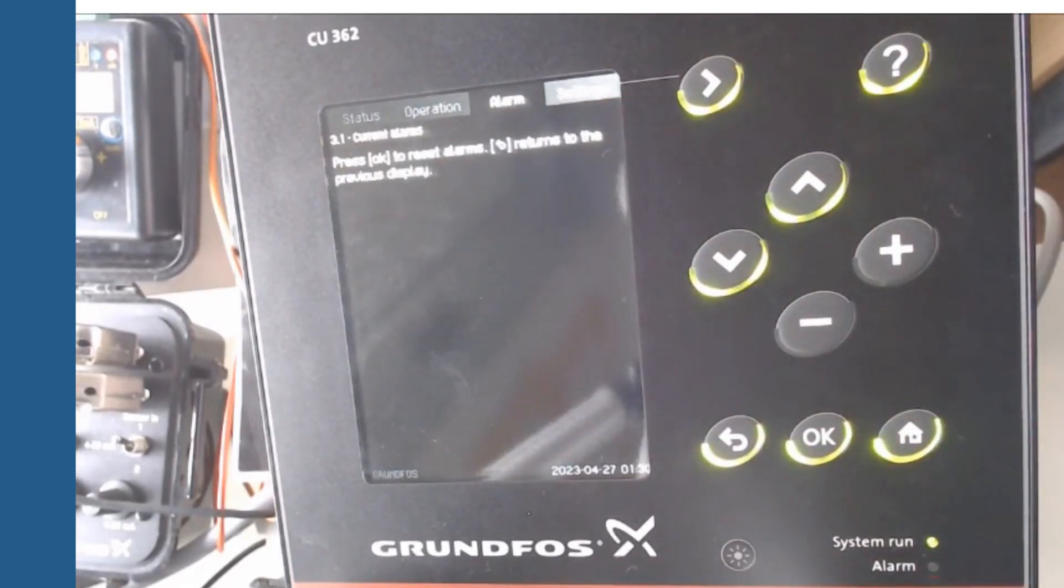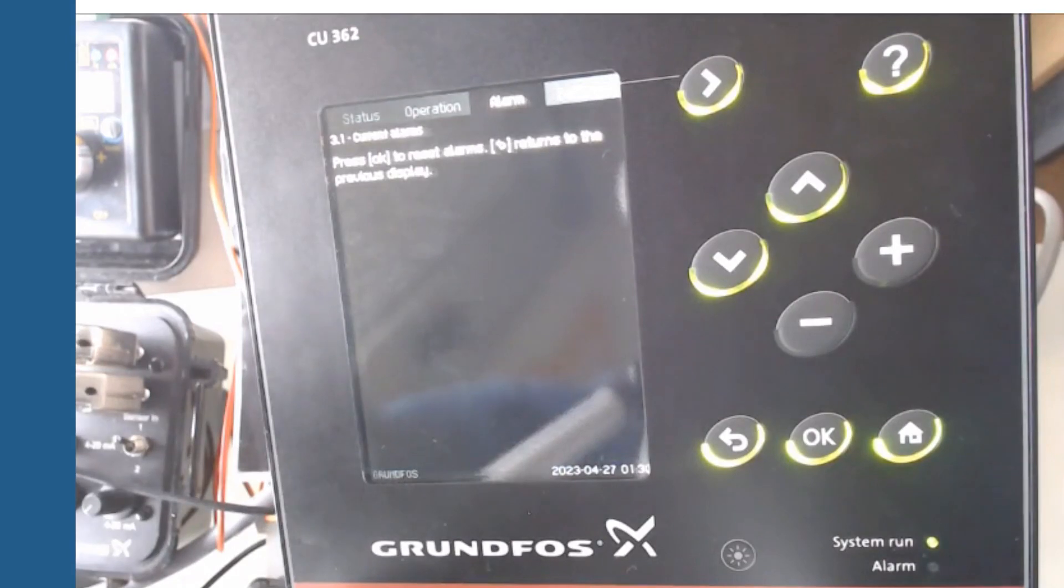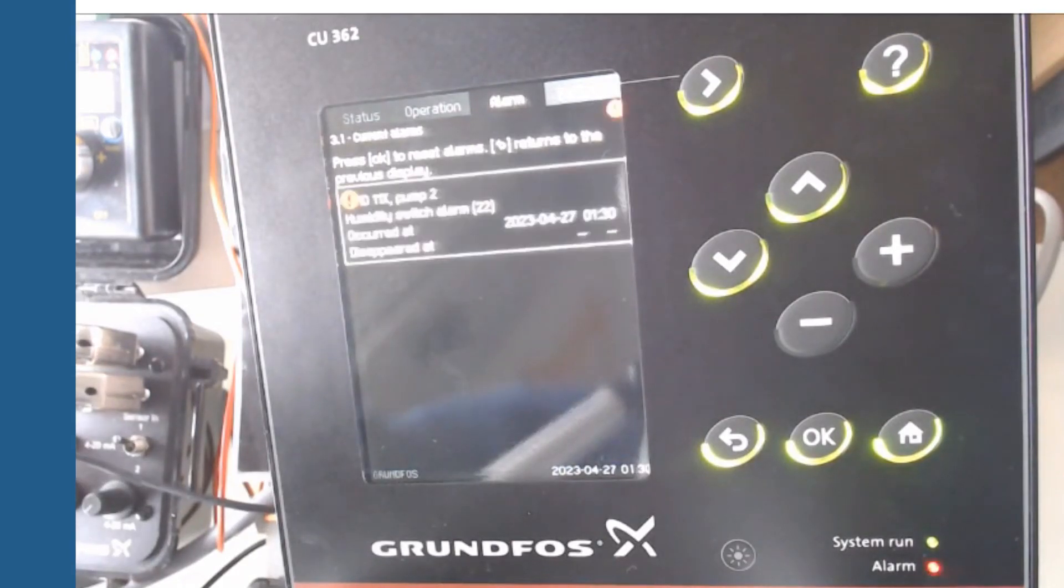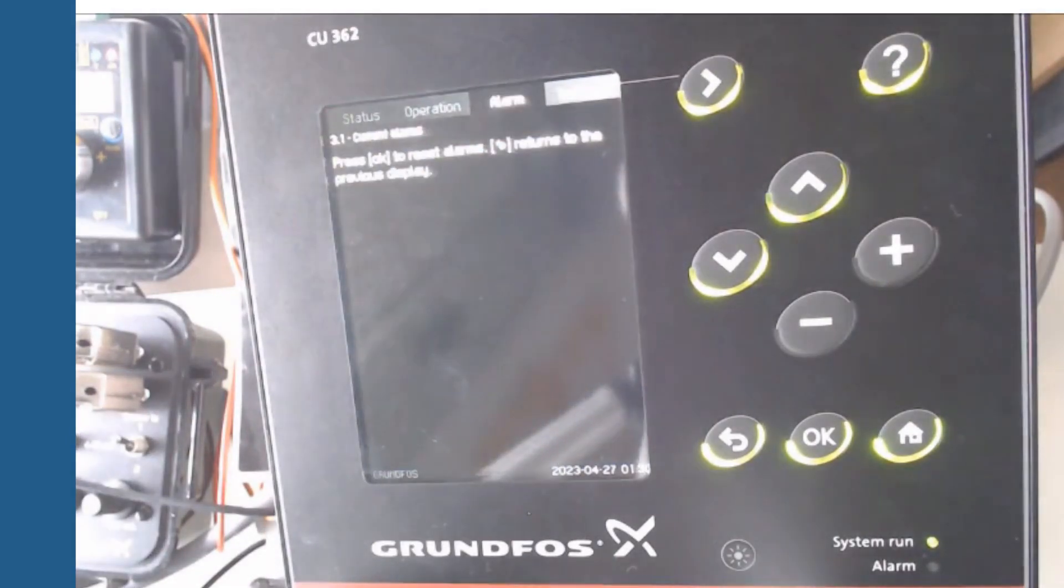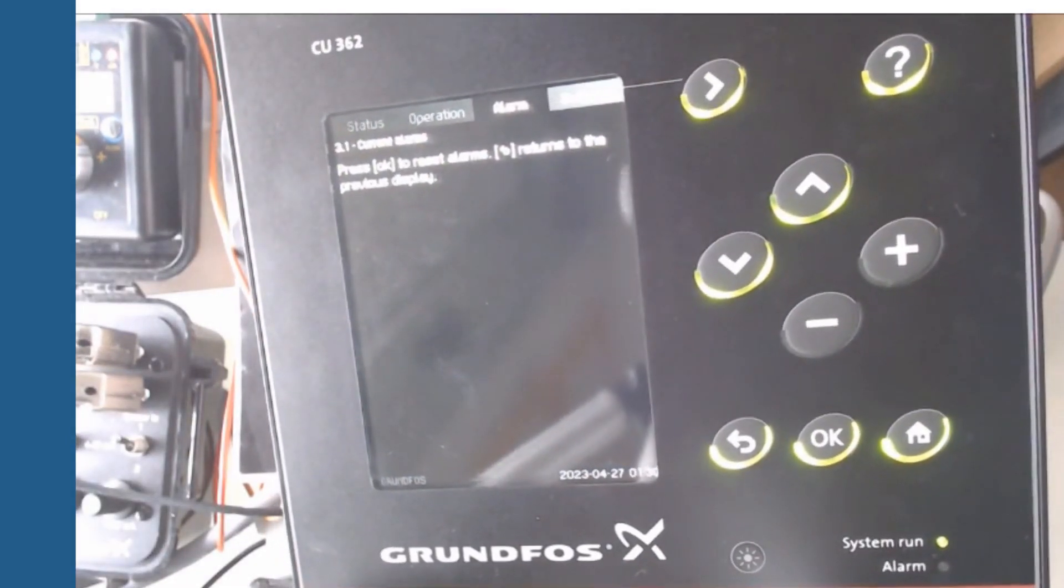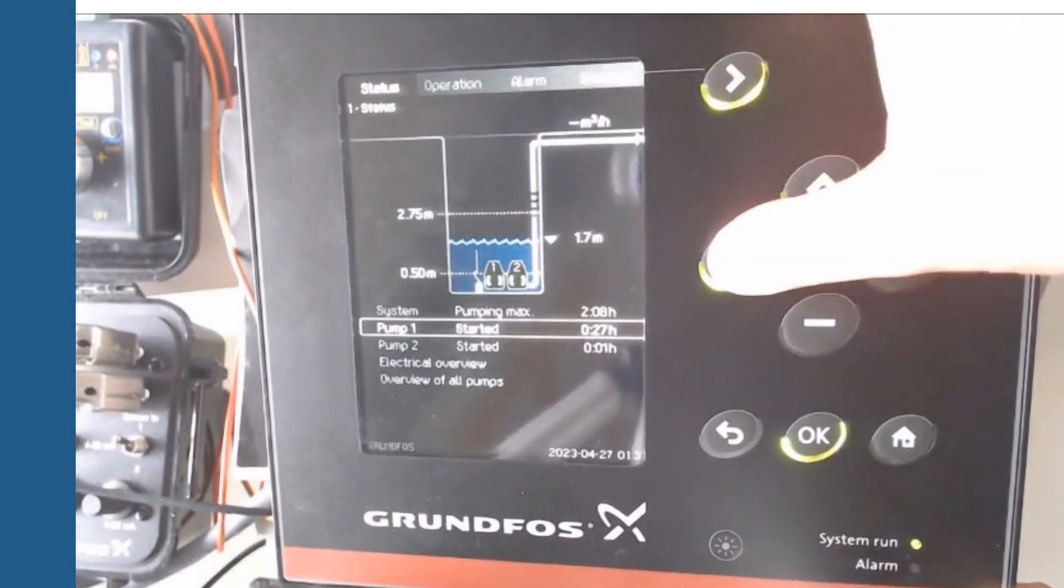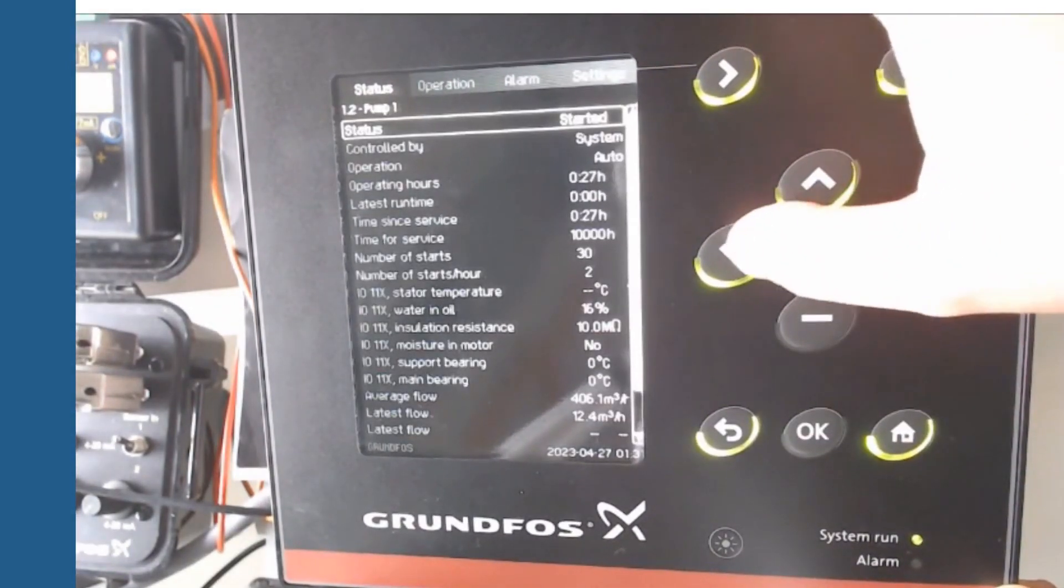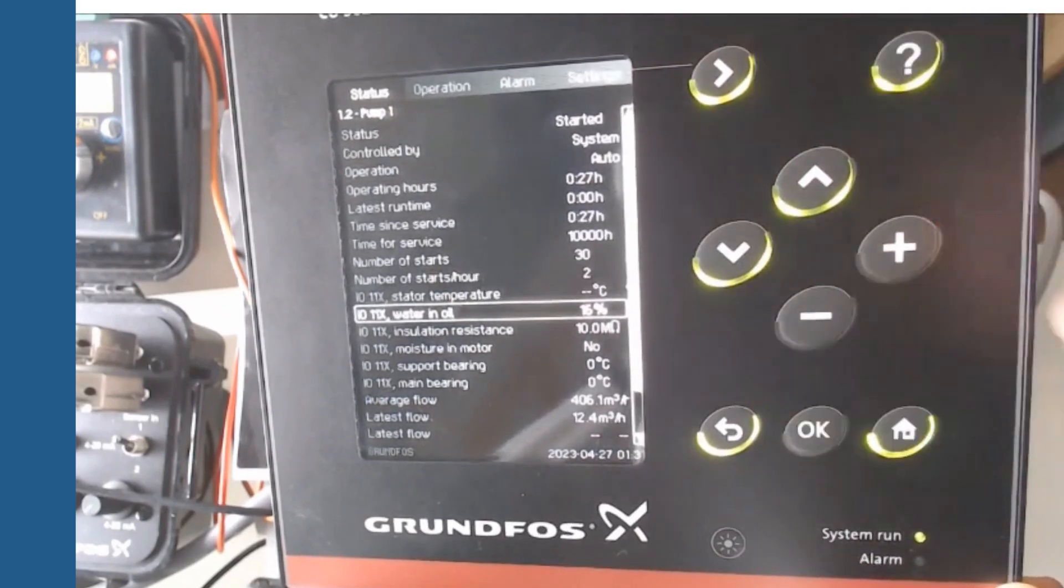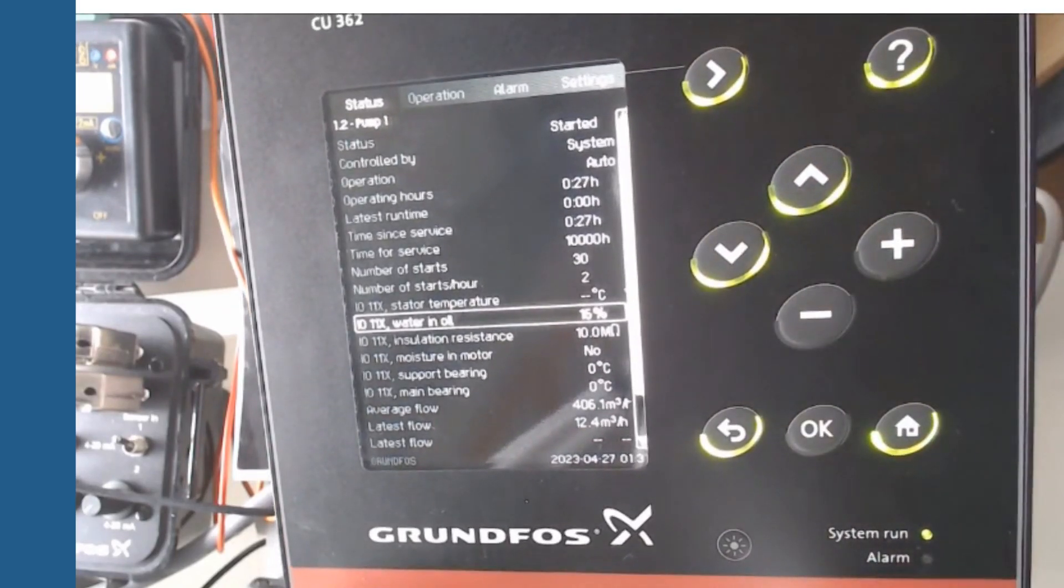First, we tested the PTC and moisture switch in pump 1. The system will alarm you meanwhile the IO-113 transmitted that status. After pump 1 we are doing the same with the pump 2. Going back to the menu status, selecting in each pump we can access to all data from IO-113.